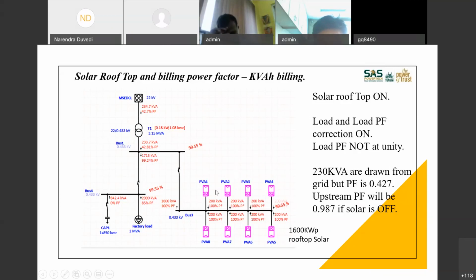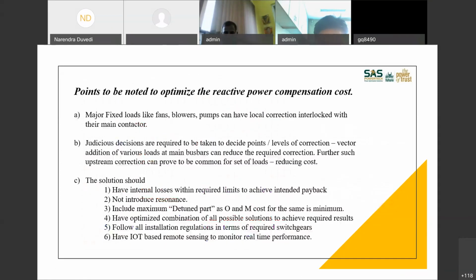So all that, if you want to compensate for your power factor and keep your billing power factor at unity, then whatever load you are running, your power factor should be as close to unity as possible. So that additional reactive power is not demanded from the grid. This is as far as the effect of solar plants is concerned. So I have almost come to the end of my presentation.